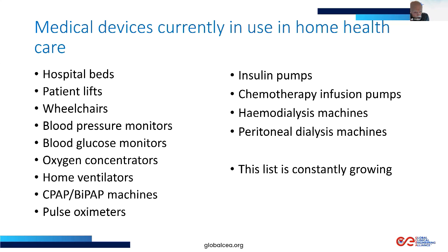I'll talk a bit about just wheelchairs, because it sounds like a pretty simple device, and how could you harm anyone with a wheelchair? So again, a coroner's investigation. The patient had a power wheelchair. They also had a work table because they were involved in some creative arts. Unfortunately, the work table was installed at just the right level so that the joystick on their power wheelchair could become jammed under the bottom surface of this work table.